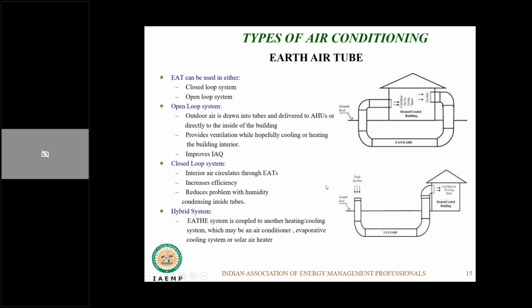The other way of using it is an open circuit where you have fresh air coming in, you filter this air to a reasonable level and pass it through the earth air tube. Here it comes in contact with around 20 to 18 degree earth surface, loses its temperature, and cold treated air can come into the system. Now you can use this method in conjunction. When you use it in an open loop system, it adds to your indoor air quality. You can add a lot of fresh air to the system without adding too much air conditioning load, and you can use it in conjunction like how we use an indirect evaporative system. This is another strategy of using it.